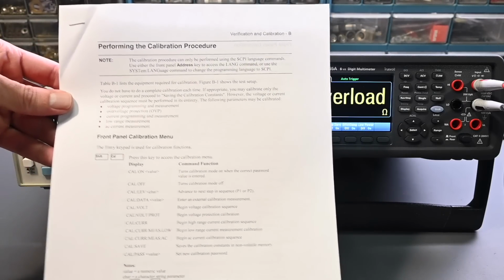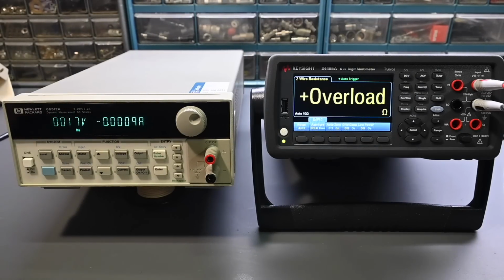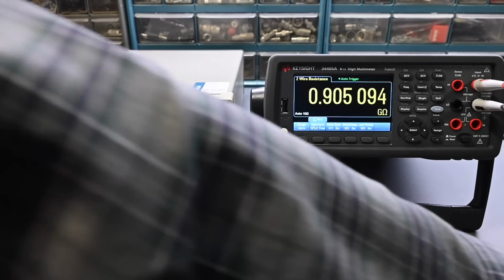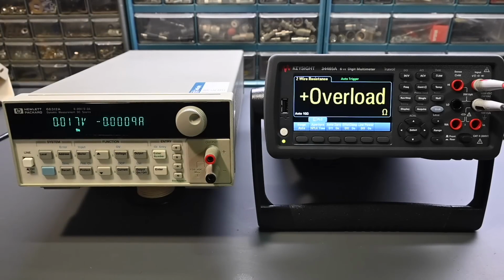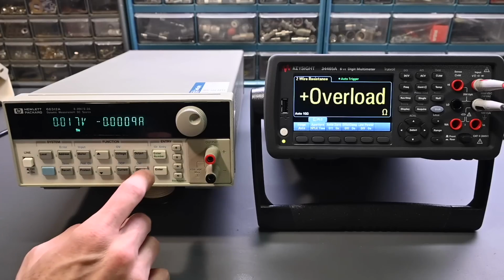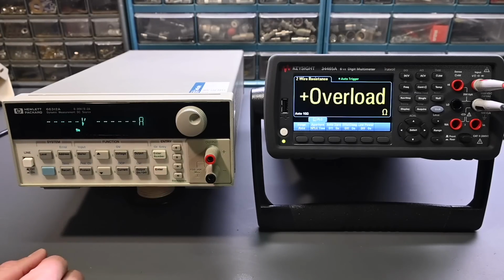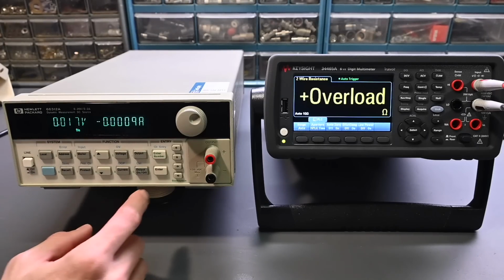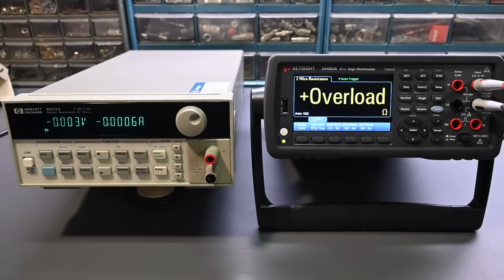So this is in the user manual, not the service manual. So let me set the test leads back over here. So the first page is just explaining some menus to go through, and then the second page gets started here into the calibration. So it says here, reset the unit by selecting the output, scrolling through reset and pressing enter. So select output, there's reset, press enter, so the power supply is in a known state. It says press output on off, turn the output on, there it is. So output is turned on, it's enabled.